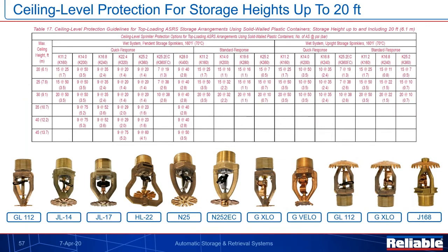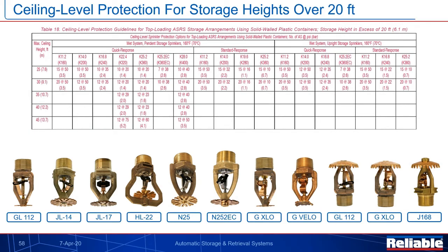All indications are that this particular storage height of 20 foot is about the max that we're going to see for this type of system. However, there is a table in there for over 20. Like I said, I just don't believe this product exists in the market right now. Everything's pretty much about 19.6 right now for storage height from, I believe, Ocado and AutoStore.